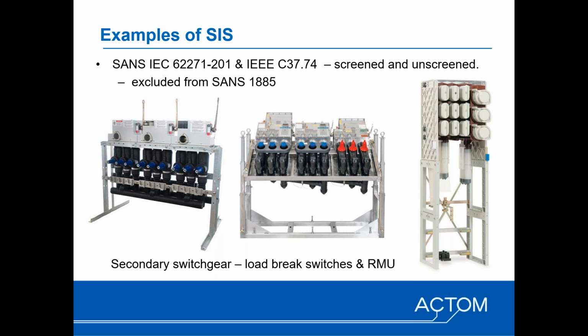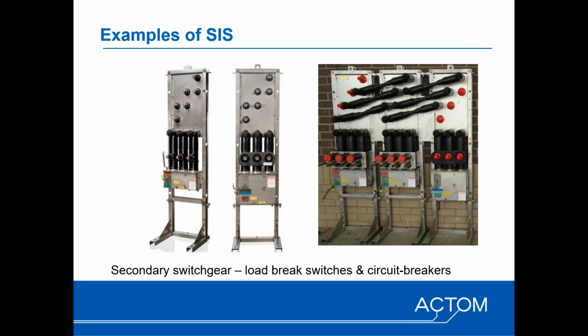On the right, those of you who've ever been involved many years back with some of the Type A mini subs, that's a ring main unit, very much of the type covered by -201. So the category of insulation enclosed medium voltage switchgear assemblies, and that effectively has a fused tee-off and two ring switches. And there are examples of those still in the network today. Here's another few good examples of screened solid dielectric switchgear, where you can see the main poles and how the different functions are then interconnected with screened solid dielectric busbar systems. And these examples again are common in the US, and they're not metal enclosed switchgear assemblies.